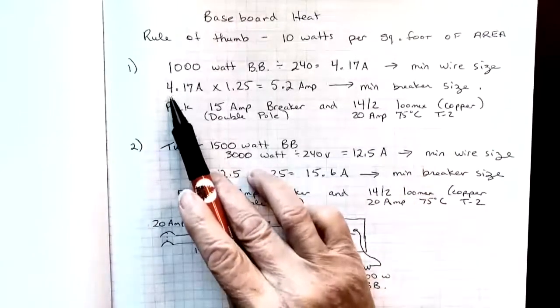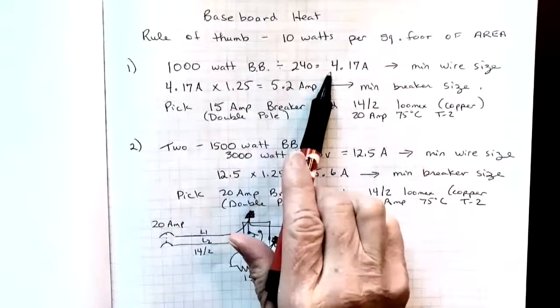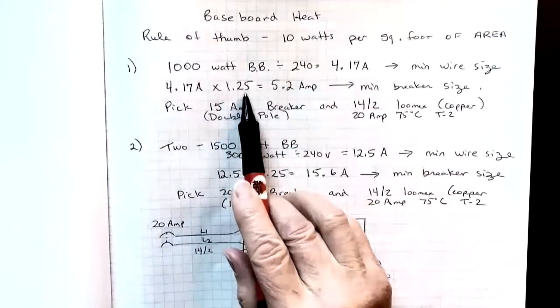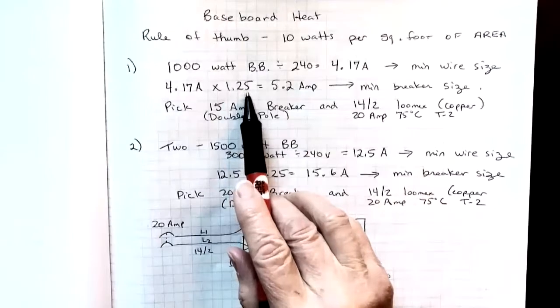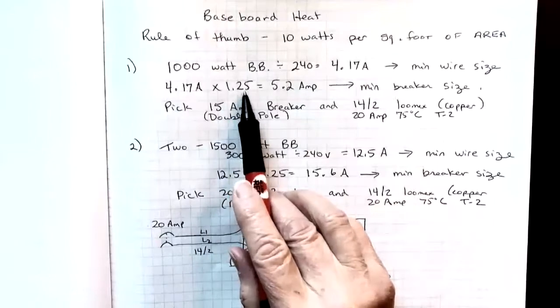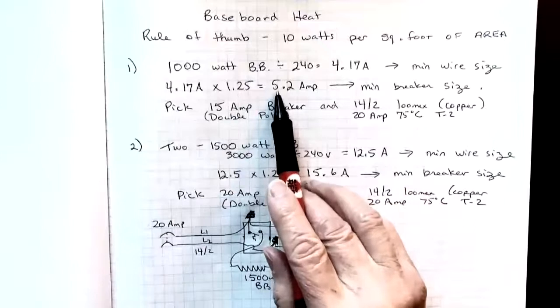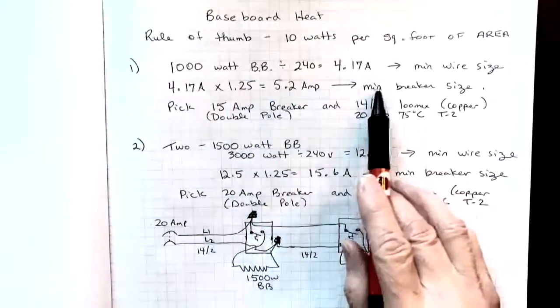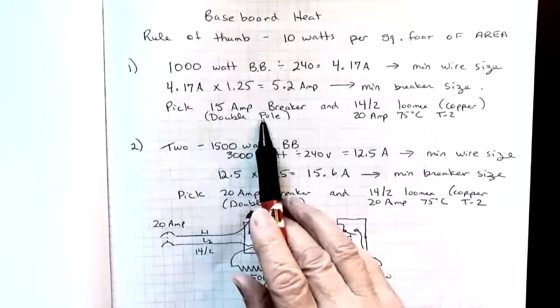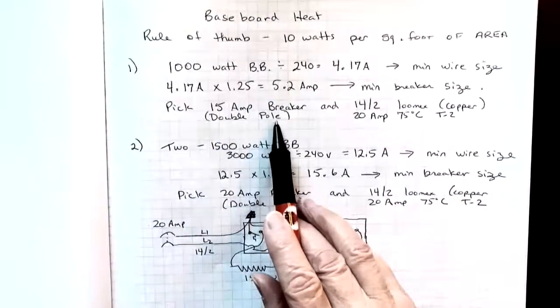To find the breaker size, I take that ampacity 4.17, multiply it by 125 percent because our standard breakers are not rated for continuous duty at 100. So we have to upsize them so they can handle the load. And we get 5.2. Our minimum breaker size, typically a 15 amp double pole breakers minimum size for homes in Canada.